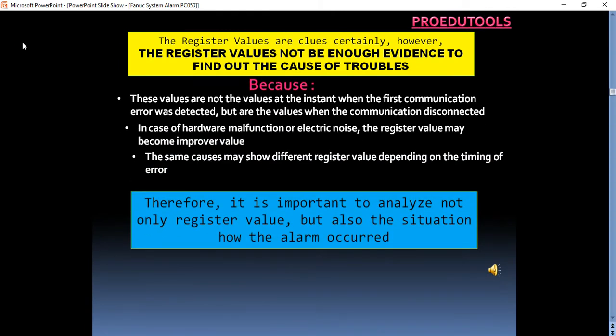These values are not the values at the instant when the first communication error was detected, but are the values when the communication disconnected. In case of hardware malfunction or electric noise, the register value may become improper value. The same causes may show different register values depending on the timing of error. Therefore, it is important to analyze not only register value, but also the situation how the alarm occurred.